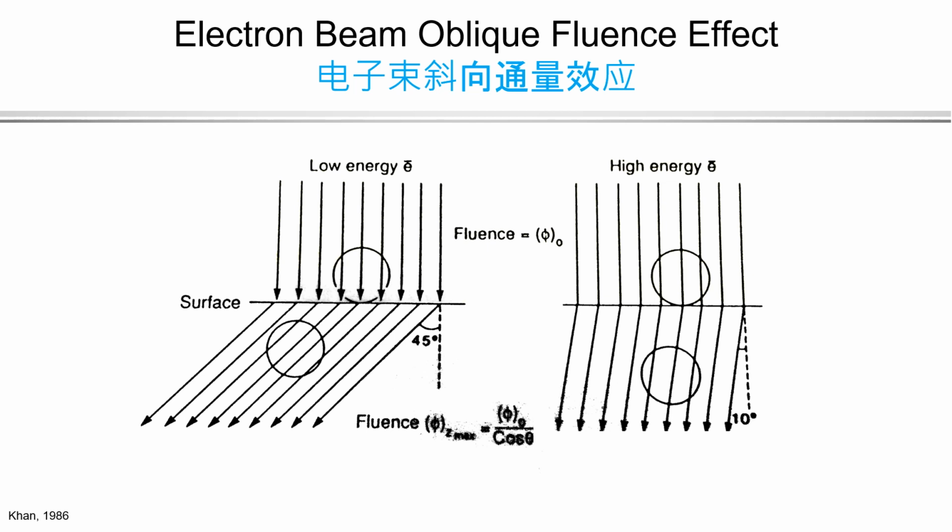This figure shows why the dose increases with depth for an electron beam. As shown on the right, for an initially high energy beam the electrons are mostly traveling forward. As the electrons cross a target, such as an ionization chamber or a DNA molecule, the dose is proportional to the number of tracks crossing the target times the length of each track. As the electrons penetrate the medium, the electrons have multiple scattering events, resulting in many tracks moving at large angles to the initial tracks, and thus more tracks traversing a target of the same size, as seen in the diagram on the left. The fluence, and thus the dose, increases with increasing depth.